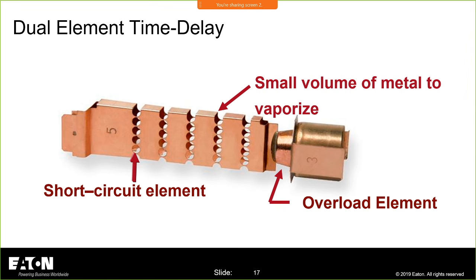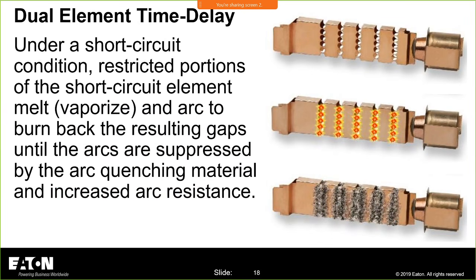And then you have the short circuit element, which has all of those small pinch points that, under very high fault currents, and remember, what I'm not showing here is that there's sand all around this, basically explode. They heat, and the sand, I mean, you think about it, when sand gets really hot, what happens? It turns into glass. We call it fulgurite. I don't mean to get vulgar with you, but it's called fulgurite, and it will basically insulate and isolate the circuit, stopping the flow of very high fault currents.